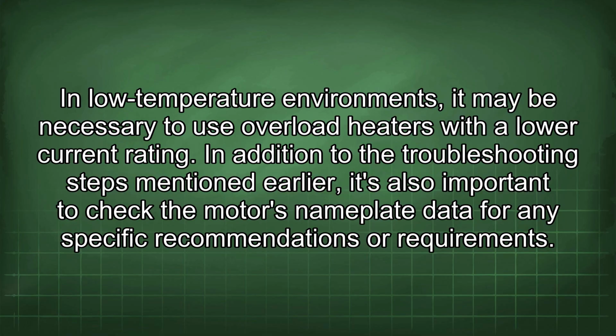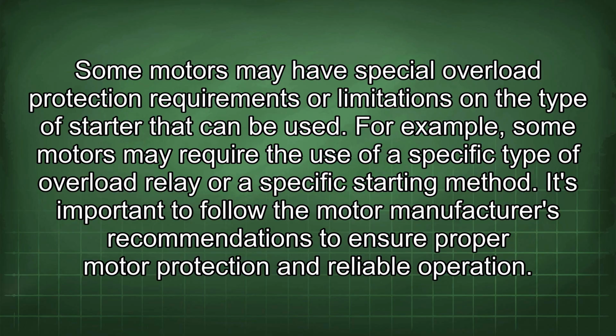In addition to the troubleshooting steps mentioned earlier, it's also important to check the motor's nameplate data for any specific recommendations or requirements. Some motors may have special overload protection requirements or limitations on the type of starter that can be used. For example, some motors may require the use of a specific type of overload relay or a specific starting method. It's important to follow the motor manufacturer's recommendations to ensure proper motor protection and reliable operation.